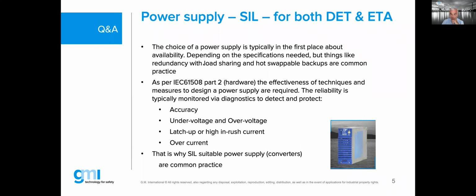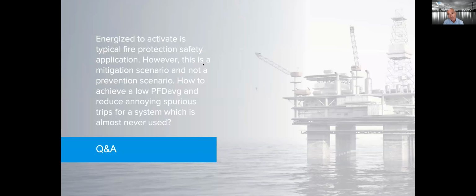Okay, I'm going to continue. Right, Tino. So the next question is: energized to activate is a typical fire protection safety application. However, this is a mitigation scenario and not a prevention scenario. How do you achieve a low average PFD and reduce annoying spurious trips for a system which is almost never used? Very complicated question.